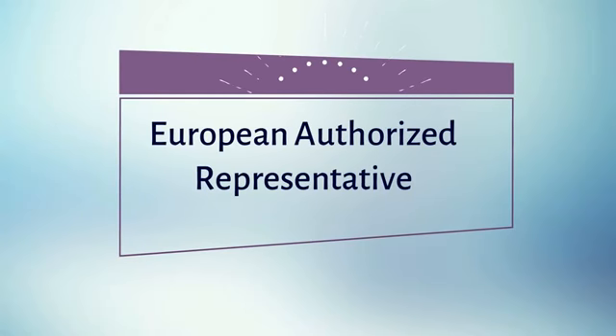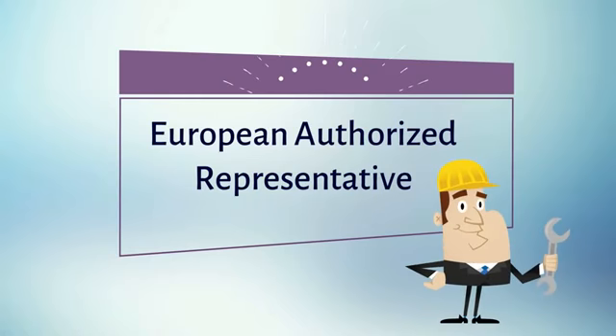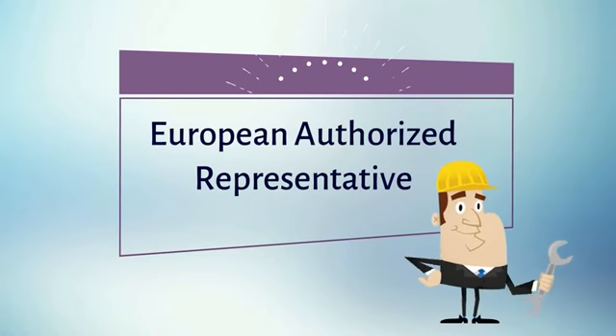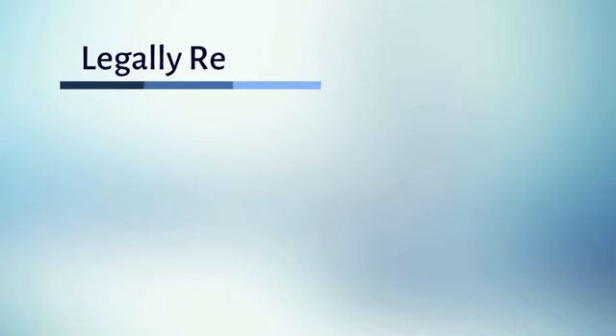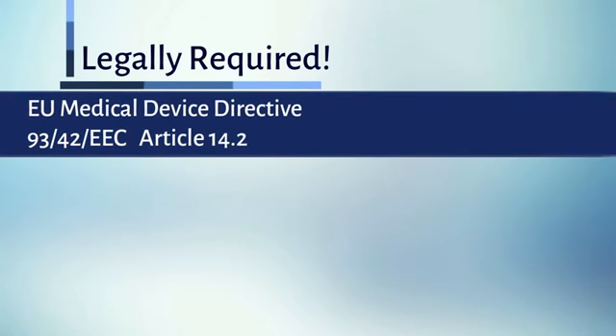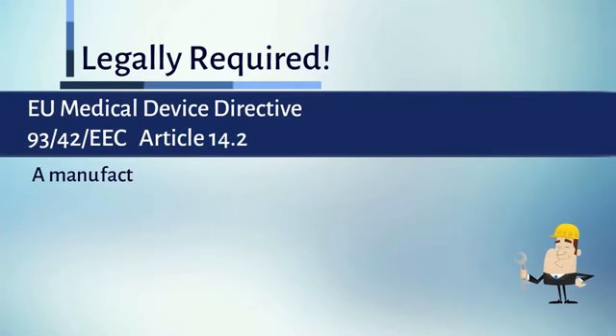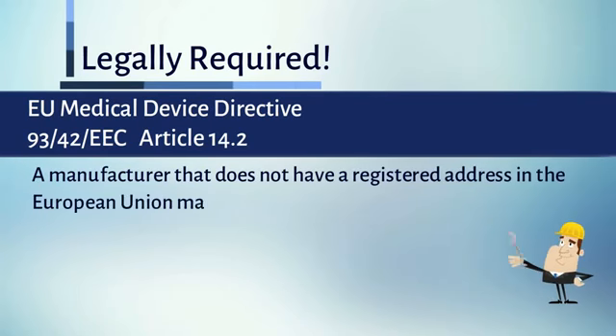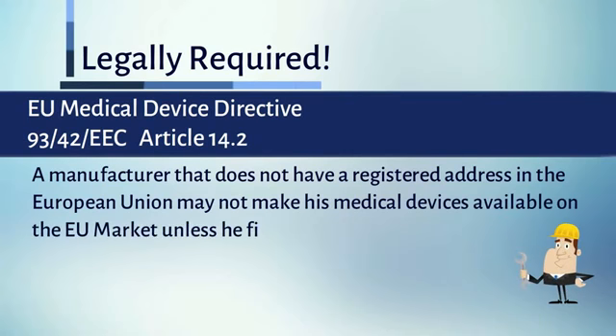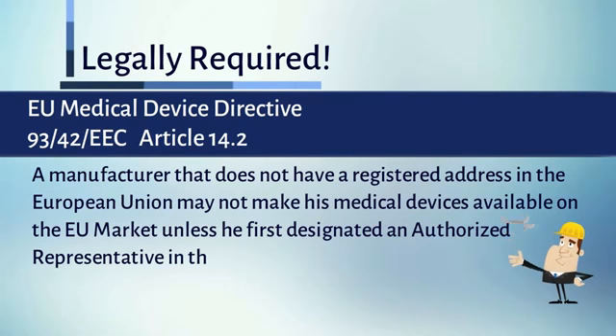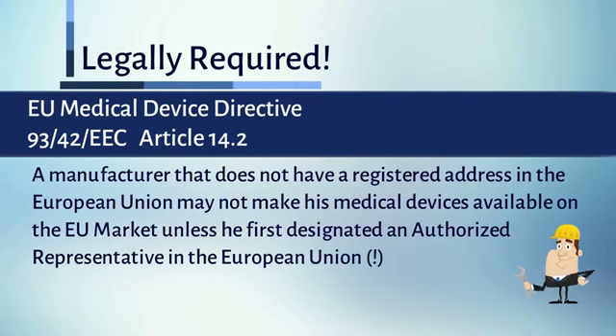The European Authorized Representative is critical for manufacturers wishing to sell medical devices on the European market. The EU Medical Device Directive, Article 14.2, says: a manufacturer that does not have a registered address in the European Union may not make his medical devices available on the EU market unless he first designated an authorized representative in the European Union.